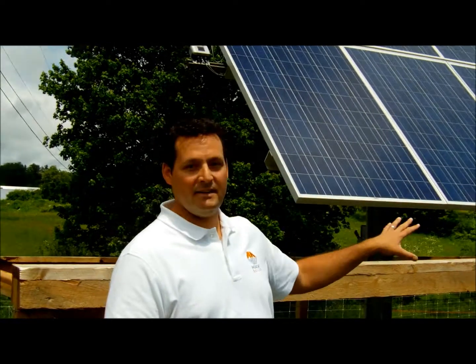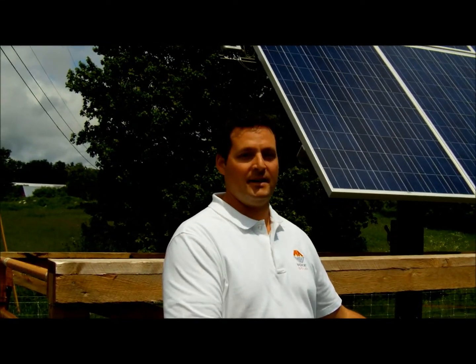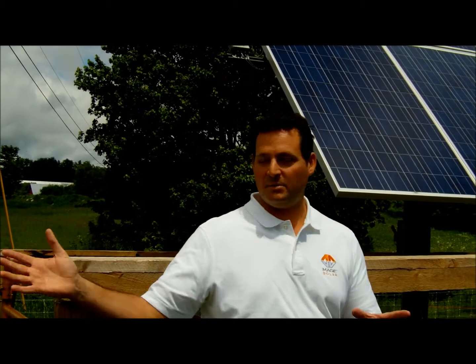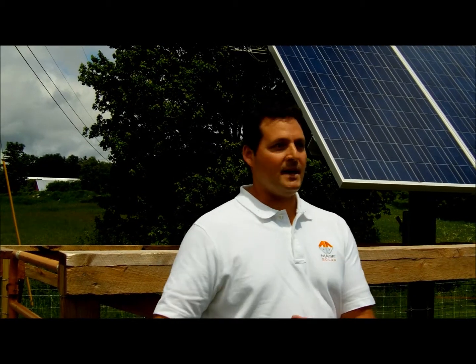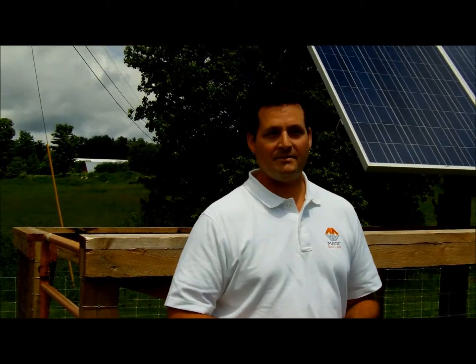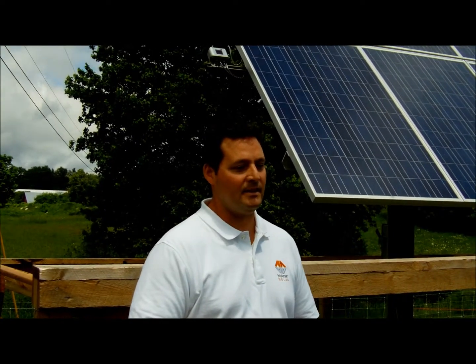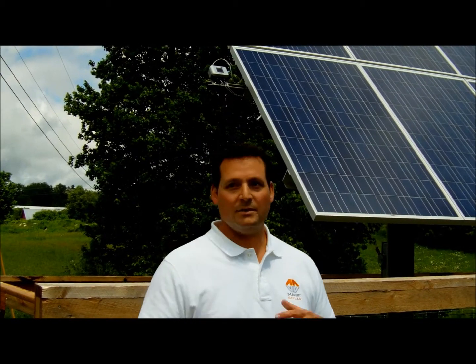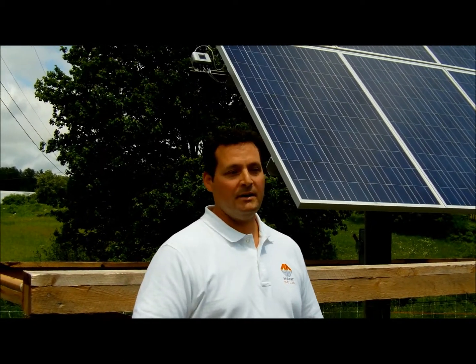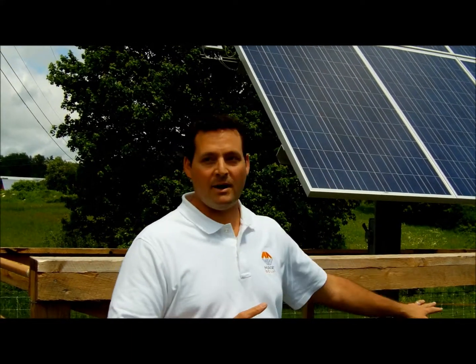This is a grid-tied array. So if the power in the neighborhood goes down, this system shuts itself down. It's for safety reasons. It doesn't continue to power the neighboring facility here. If you were to tie in part of the battery system or a battery system to it, you would typically want to have some sort of backup system. That could be done, as Bill was saying, with isolation switches, or kick out. They may have generation on site where they have generators already producing power. Yeah. But the key point here is they can utilize this power throughout the course of the year.